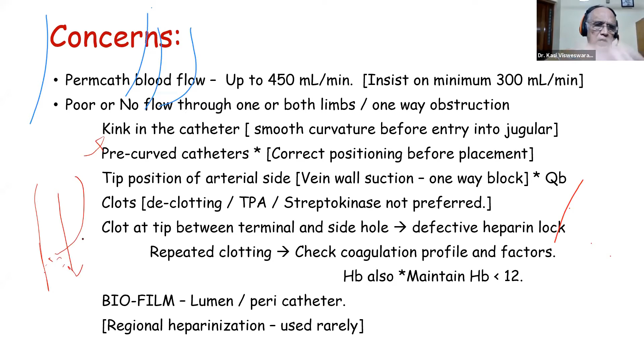And poor or no flow can be due to one-way obstruction. It can be due to kink in the catheter. We don't prefer to use the pre-curved catheters because the correct position at the time of surgery may be slightly difficult and the catheter may get twisted. Therefore, we don't prefer to use the pre-curved catheters. And then if the tip position is against the wall of the atrium, like this, the chances of suction are there, and therefore it is not preferred. So you have to position the catheter in such a way that it is facing in this direction.